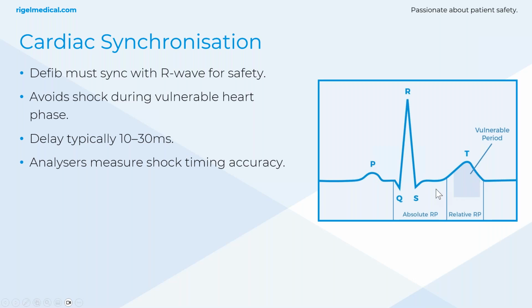So it's just making sure that the delay time is after, and analyzers will measure that timing accuracy. These defib analyzer tools allow us to measure that delay time between when it sees the R wave, or with the analyzer it's actually simulating the R wave, and then making sure that the energy is delivered within that specification.